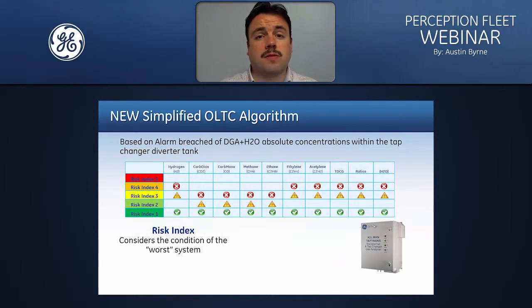We also have a simplified OLTC algorithm, and again it's based on alarm breaches for DGA and moisture. So we look at the alarm levels that are set within the tap changer for the diverter tank, and then we can apply a risk index for those particular measurements, determining what the risk index is for the asset when an alarm is triggered.